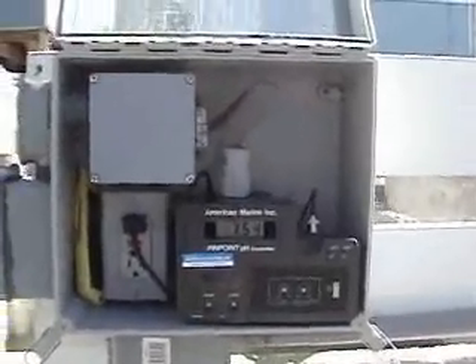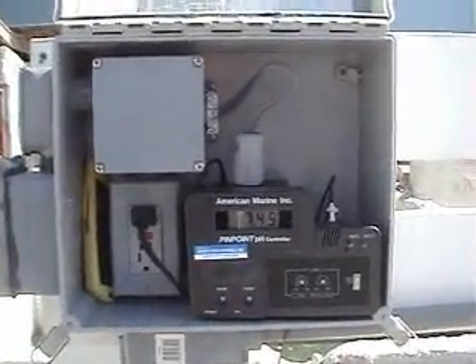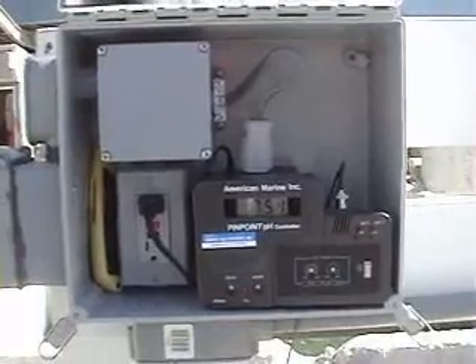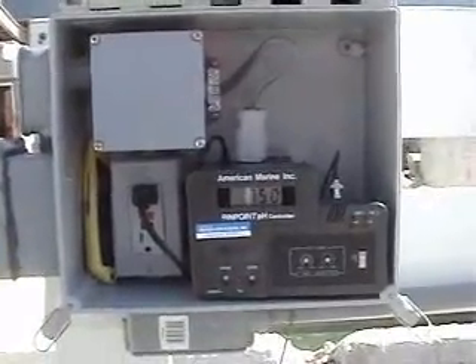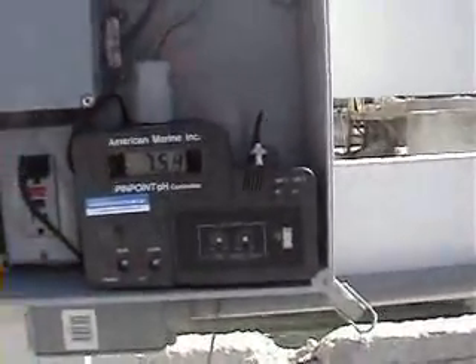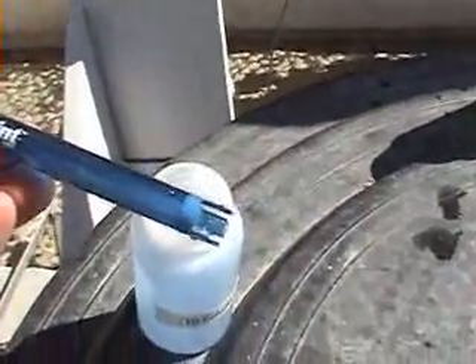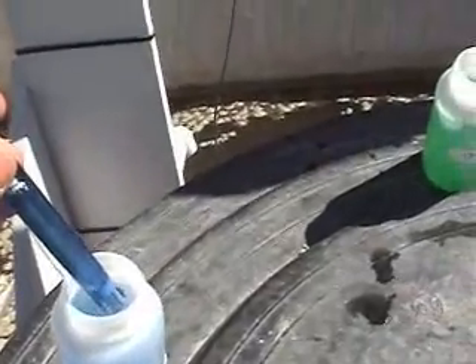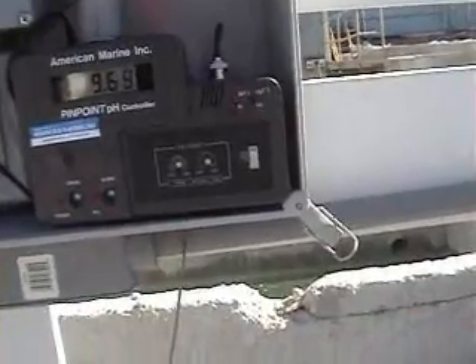Okay. Now with our pH watchdog here, we've already completed the cycle and we have a fair pH of around 7.5. Now since the cycle has already been completed here, I'm actually going to set up a little example cycle using some of our calibration fluids here. Now again, we're at a pH of about 7.5. Now when I take my probe here and I insert it into our 10 solution, we're actually going to see the system activate as if there was a pH of 10 in our treatment area.